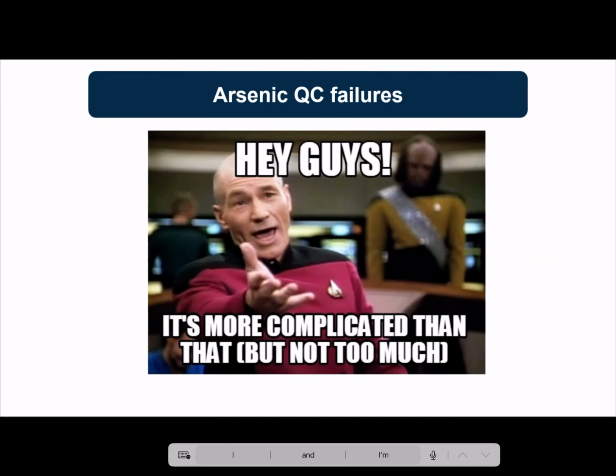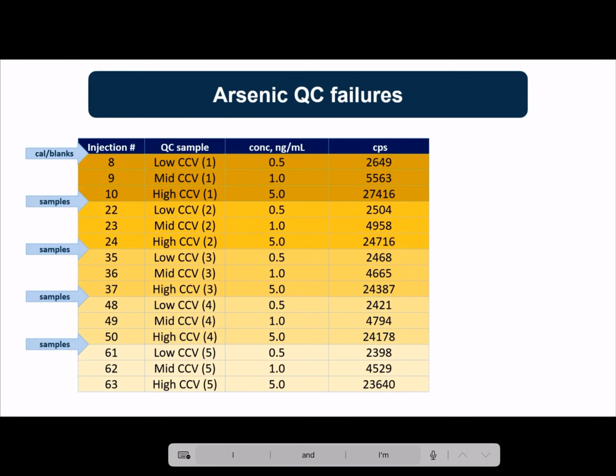Well, it's a little more complicated. So I wanted to tell the story first, and then get into the fact that it was a little bit more complicated. In this scheme, he was running 3 CCVs: a low, mid, and high. That set of low, mid, high CCVs was run every 10 injections. So the queue ran calibration blanks, the first set of low, mid, high CCVs, 10 samples, another set, 10 samples, another set, and so on down.